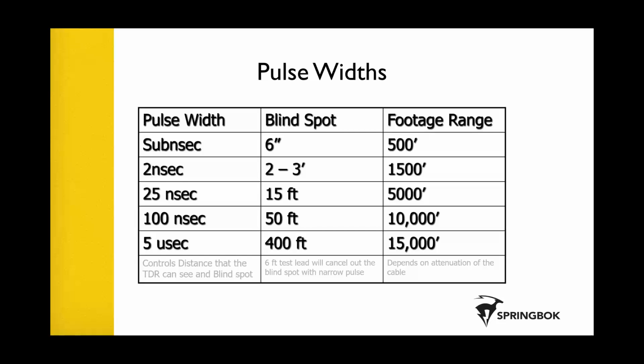Or maybe that first signature that I'm coming across is water. Everybody always wants to know what the shape is like. I want you to pay attention to what the signal's doing, right? So water is going to suck up your signal like a son of a gun. So maybe that's where my water problem is. But regardless, we understand maximum footage range.